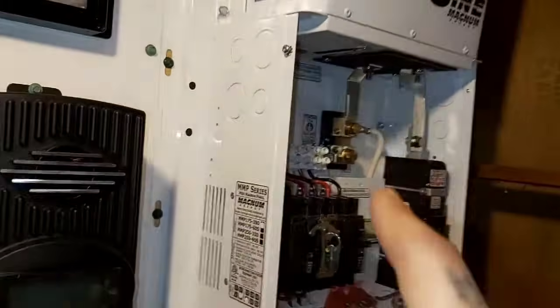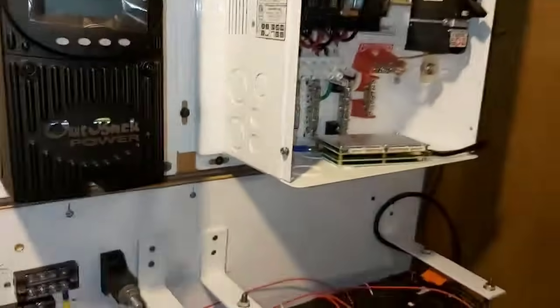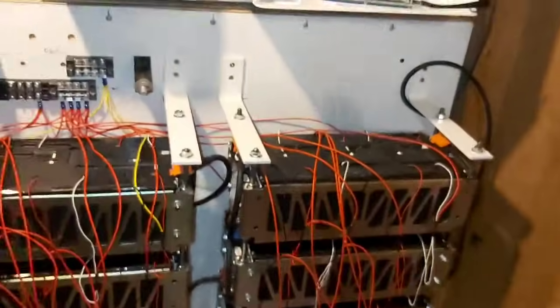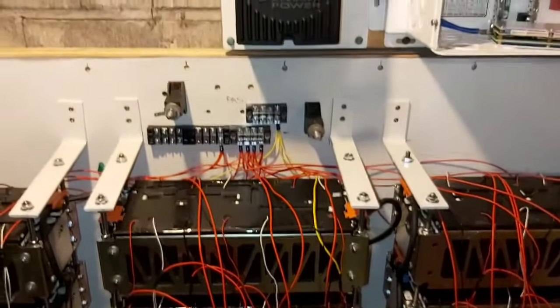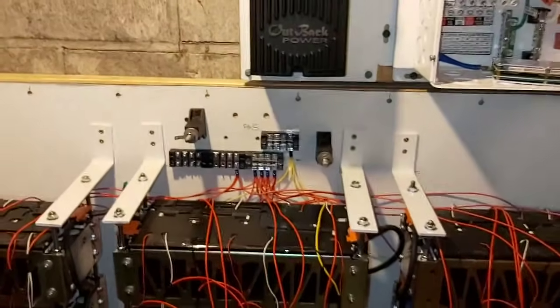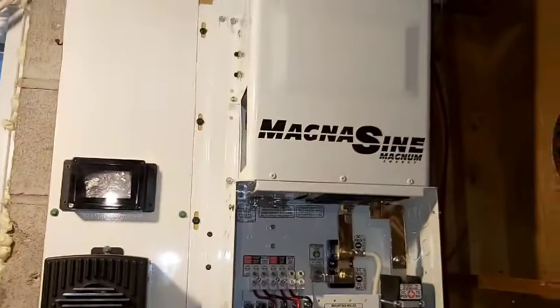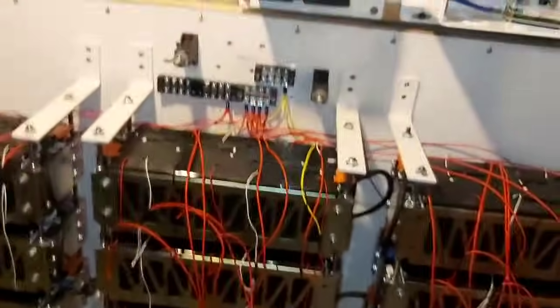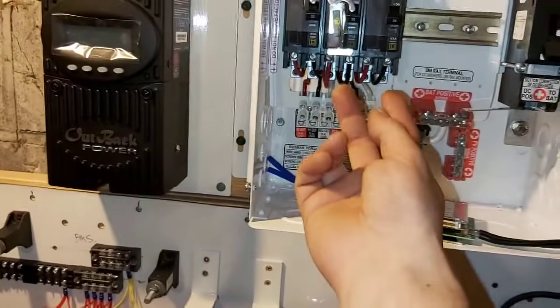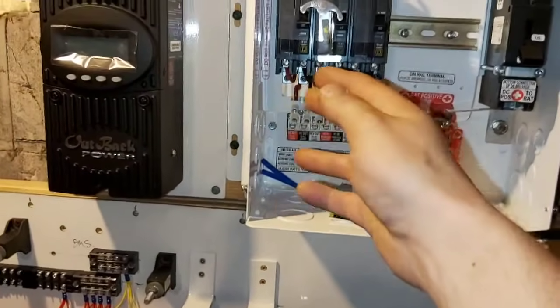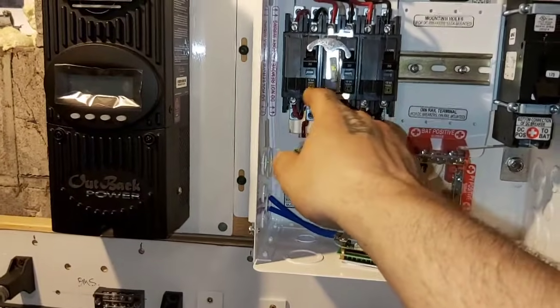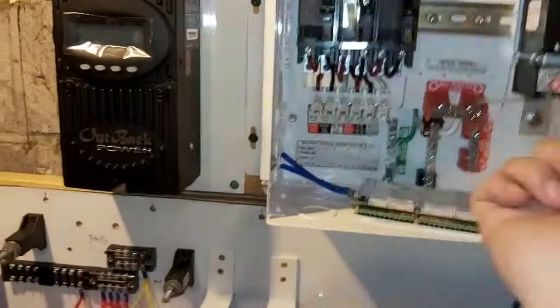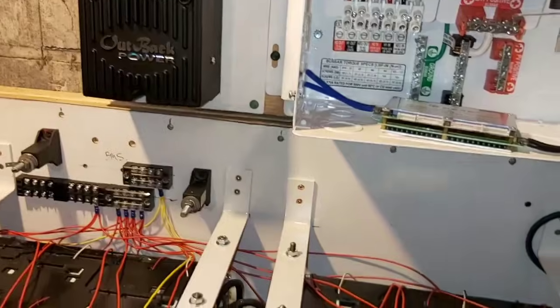We're gonna get rid of that transfer switch over there, because this has its own transfer switch. And that one out there, the existing transfer switch, took 15 seconds to actually get power back. This is 16 milliseconds. So we'll keep it on standby mode with the AC input on, and then when it senses that there's no input there, it'll automatically switch over.